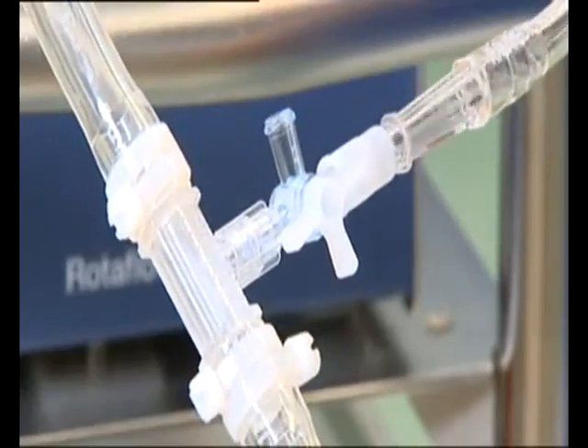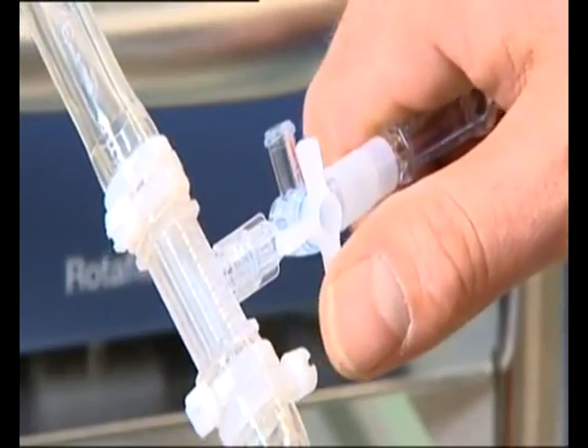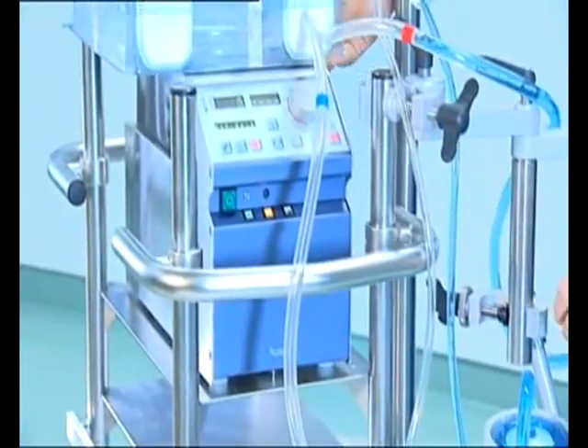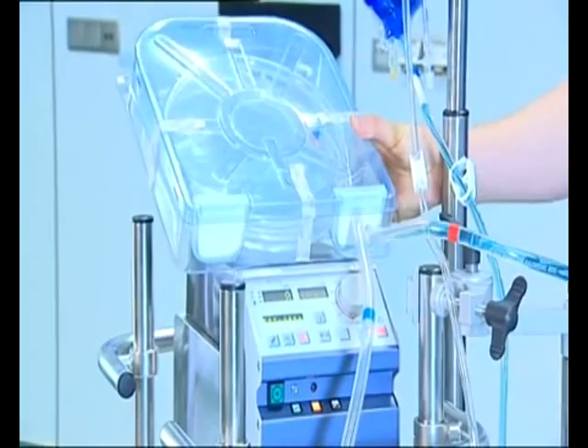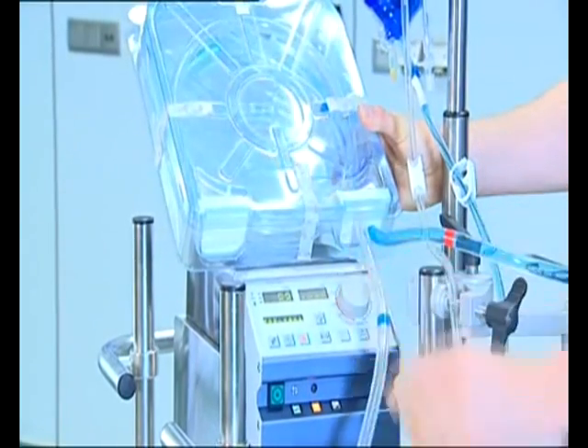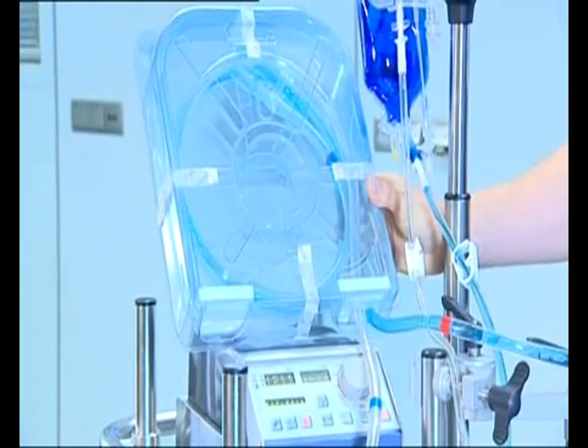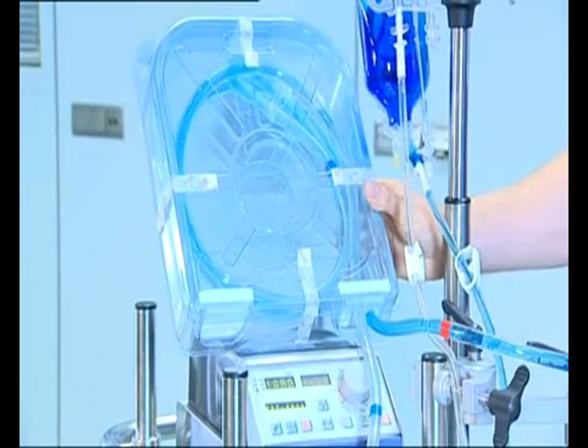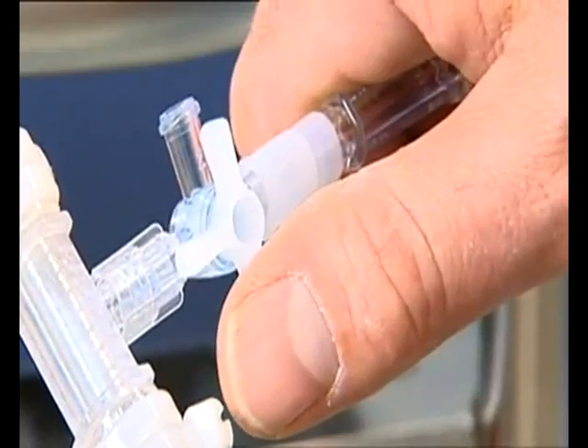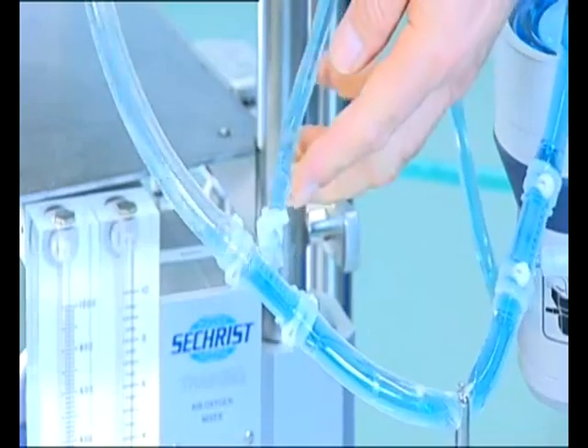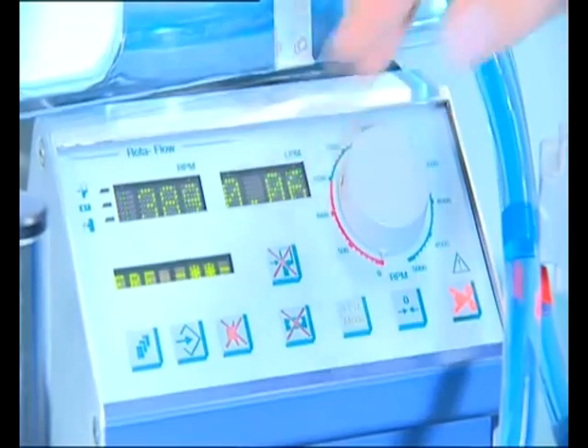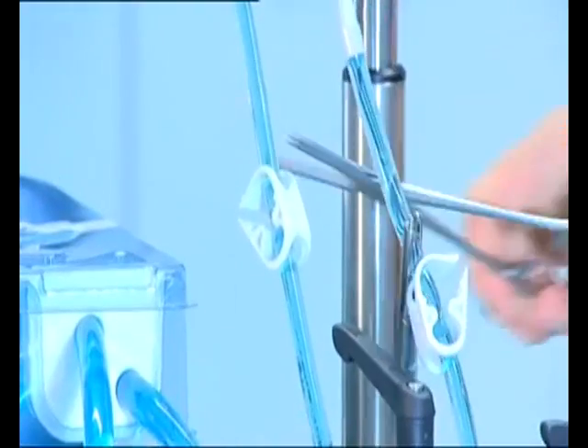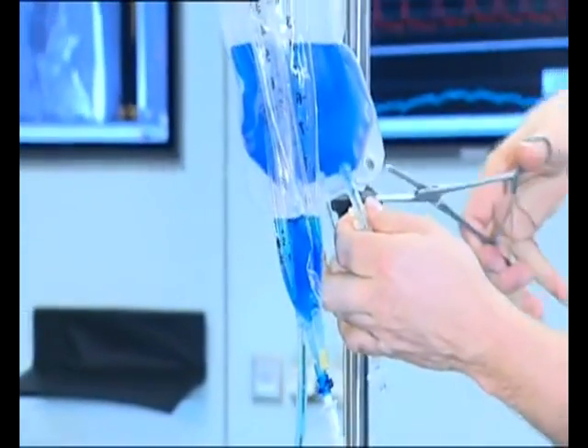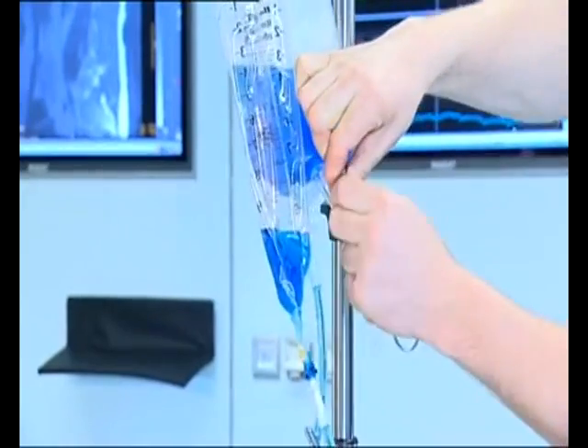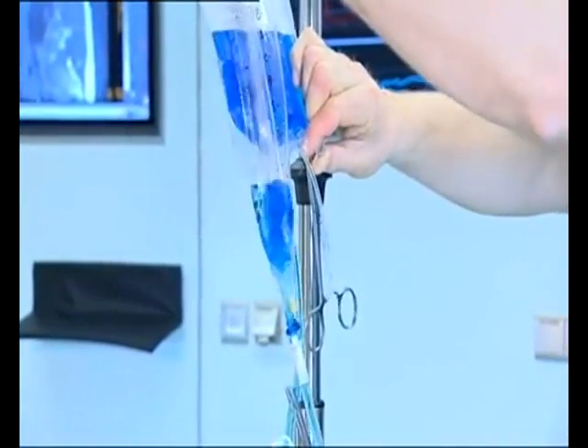First, the 3-way stopcock on the priming line nearest the box is opened so that remaining air in the lines can escape. The centrifugal pump is now used to actively start priming the lines in the box. When most of the air has escaped and the priming solution reaches the three-way stopcock, it is opened to direct flow toward the priming bag. The nearly empty infusion bag is now removed, and the line spike is attached to the priming bag.